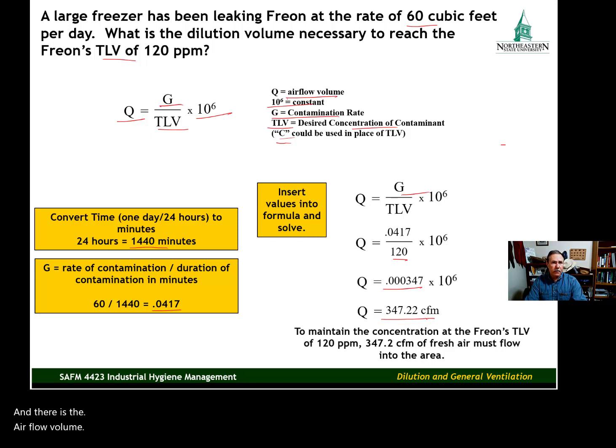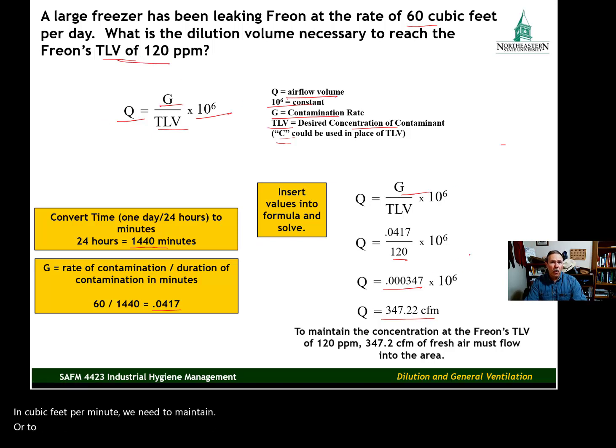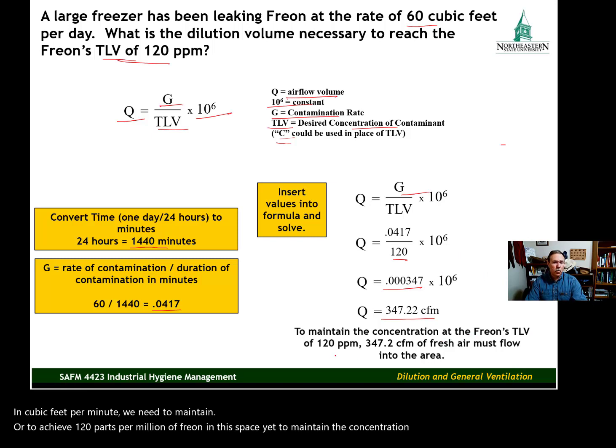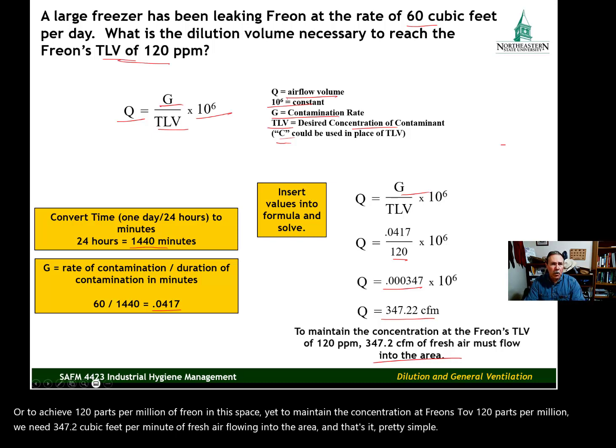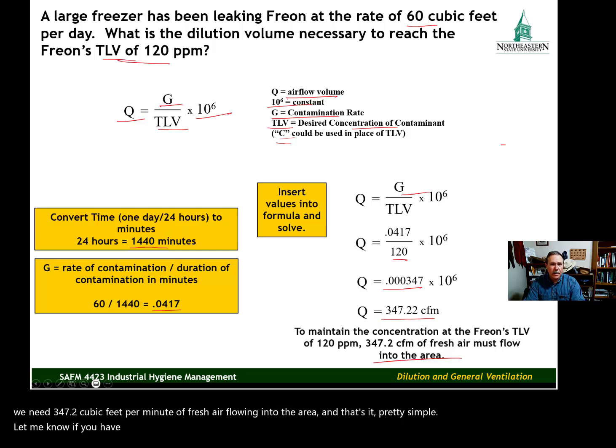To maintain Freon's TLV of 120 parts per million, we need 347.2 cubic feet per minute of fresh air flowing into the area. That's it — pretty simple. Let me know if you have any questions and I'll see you next time.